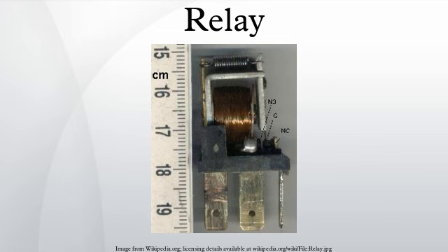Usually this force is provided by a spring, but gravity is also used commonly in industrial motor starters. Most relays are manufactured to operate quickly. In a low-voltage application this reduces noise. In a high-voltage or current application it reduces arcing.